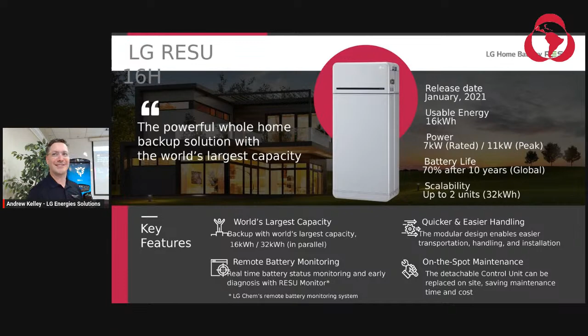Now, if you install two batteries together in parallel, and you have a 10 kilowatt hybrid inverter, you could effectively operate at a continuous 10 kW. So that's possible with two, specifically with the SolarEdge, they're 10 or 11.4. That one you're capable of operating at 10, but effectively 7 kilowatts is your continuous. 11 kilowatts for 4 seconds.